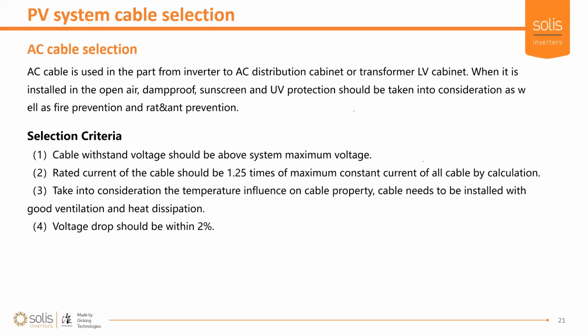And then lastly, this is the most important one for the AC side, the voltage drop of the cable. Because the cable does have a resistance associated to it, when it's got a current running through it, it's going to have a voltage drop over it. And if that voltage drop is too high, the inverter will see a much higher voltage than is at the transformer, where the loads are. Where it didn't need to disconnect, it will disconnect or stop or generate less power. So yes, you need to make sure that that cable running between the inverter and the grid connection is sized correctly, and that you have less than 2% drop.